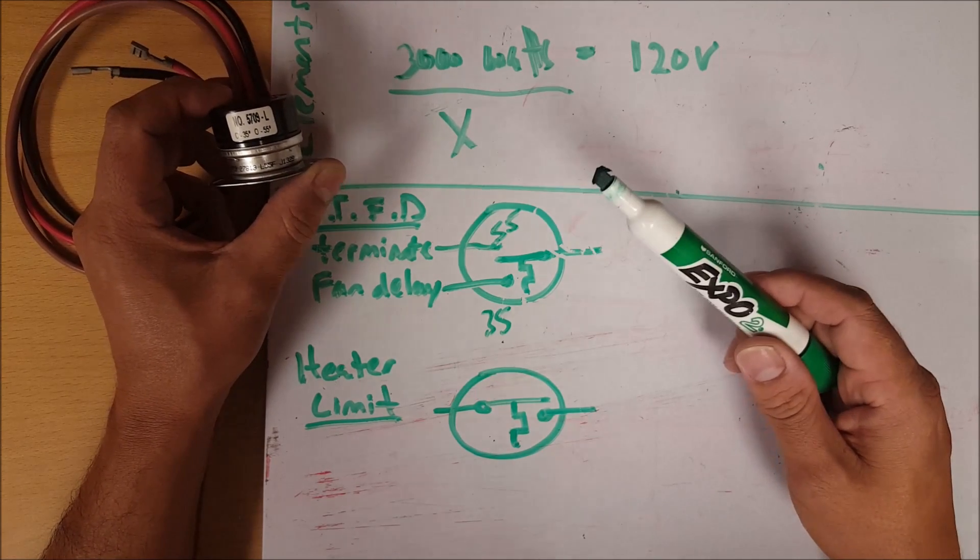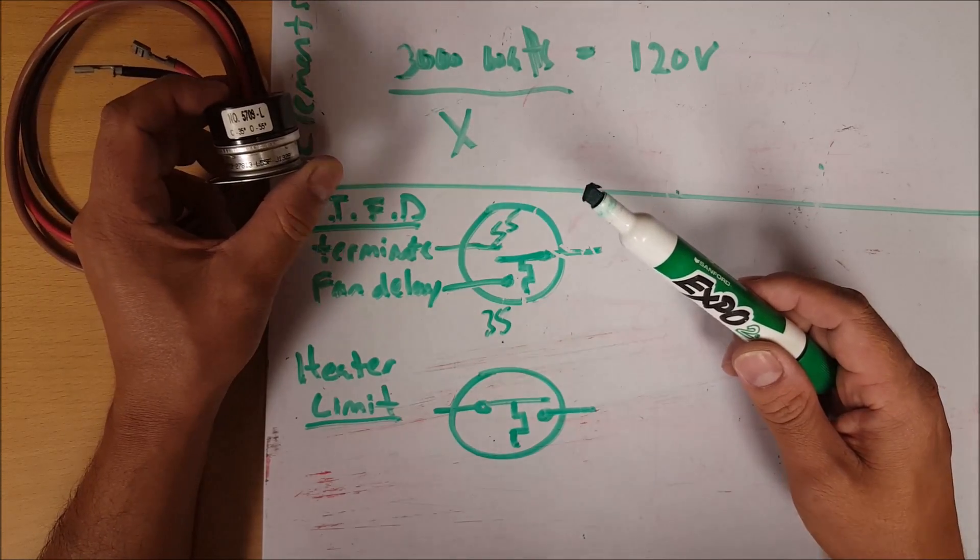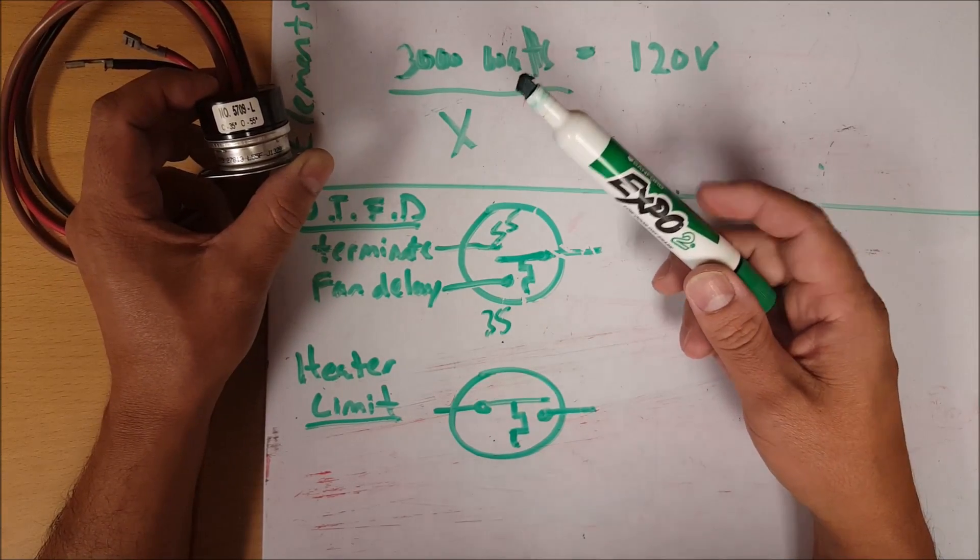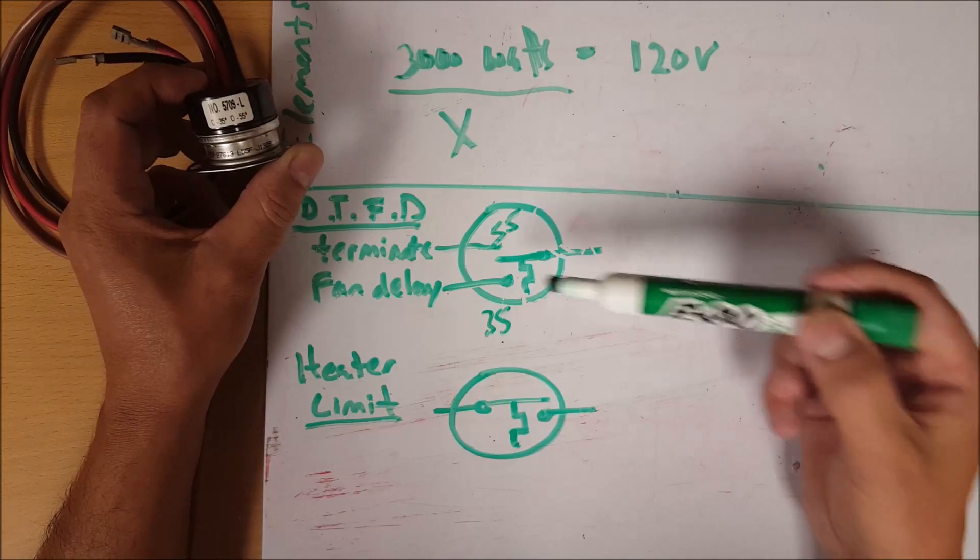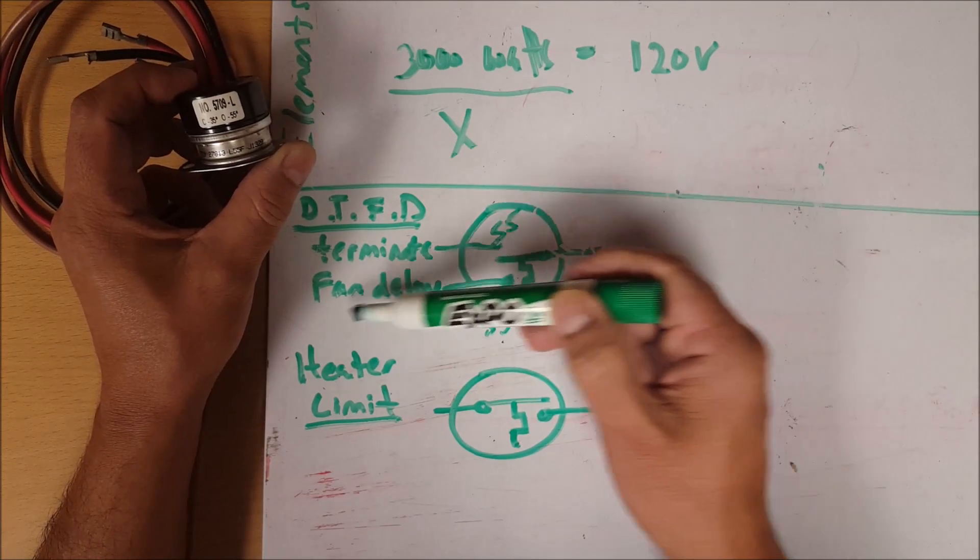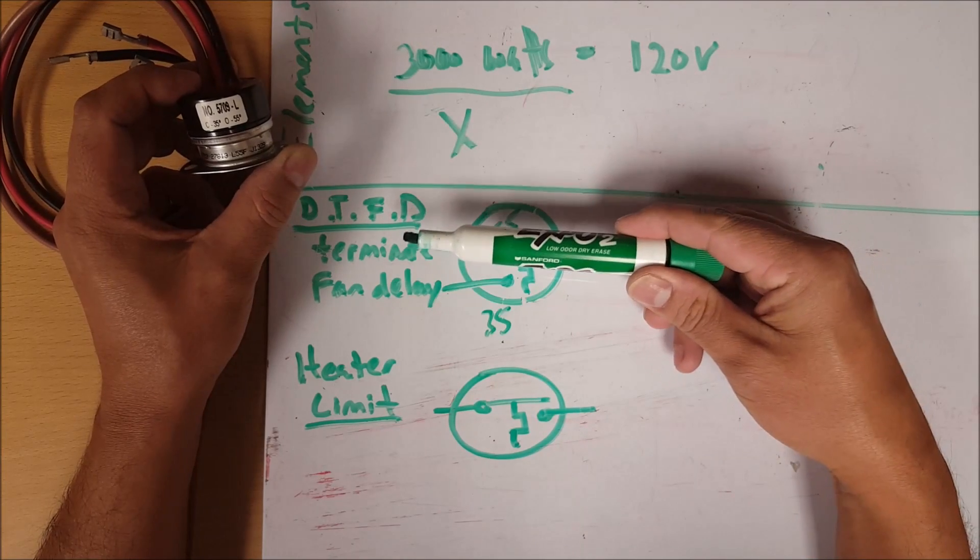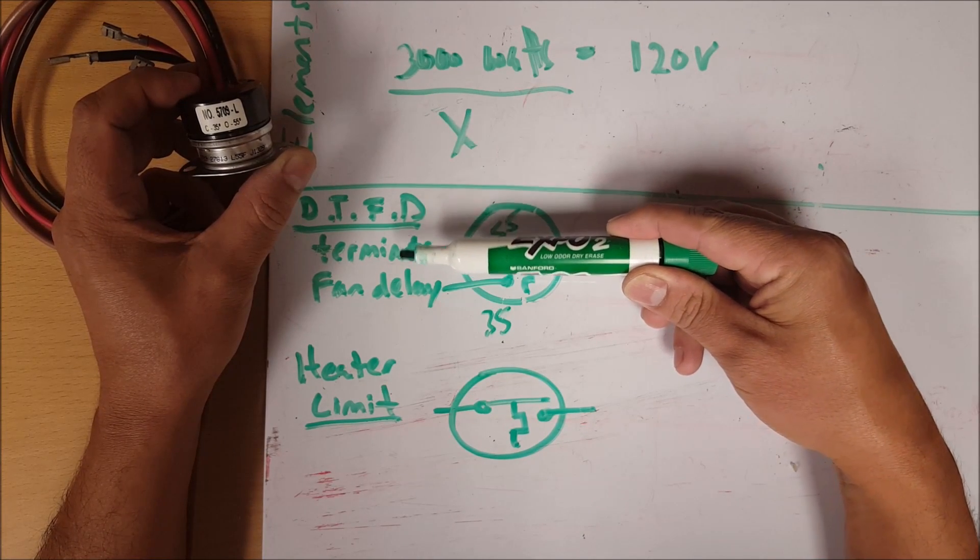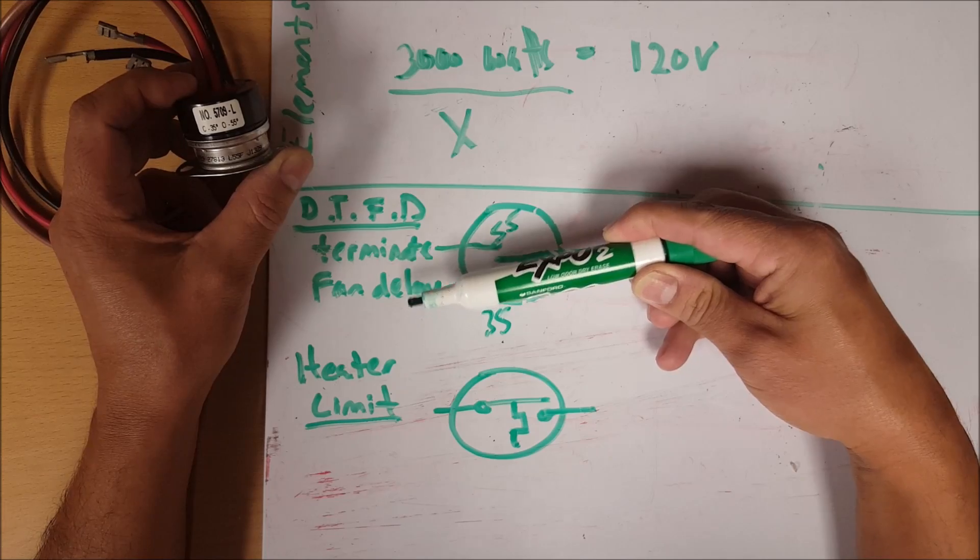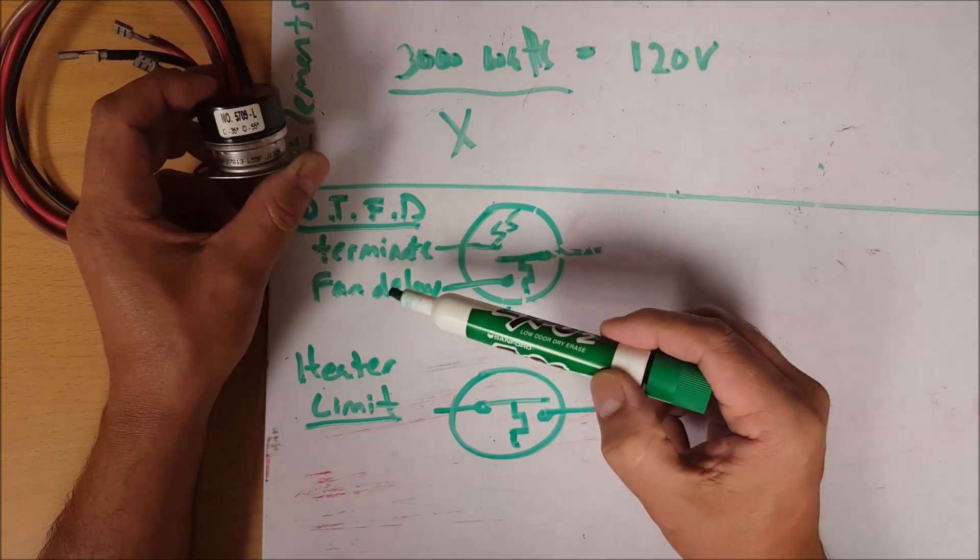Once your refrigeration system begins to run, your evaporator is going to get cold again. Your fans are not going to come on because this switch is still open. This wire runs in series with your fan motors. Once the temperature of that coil or this switch hits 35 degrees, then this completes the circuit and your fans come on.